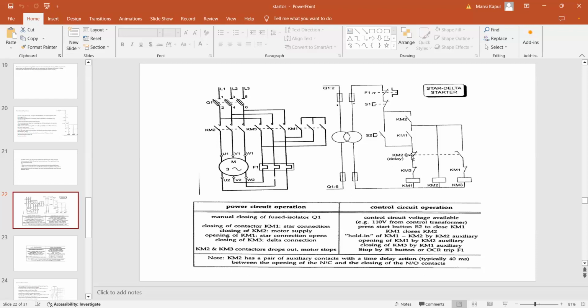So there is a time delay, KM2 latch is acting as a time delay. KM2 has a pair of auxiliary contacts, so there is a pair of auxiliary contacts, this is one, this is the other one, right? Two, that's why they are saying pair of, with a time delay action, typically 40 milliseconds between the opening of the normally closed and closing of the normally open contact.